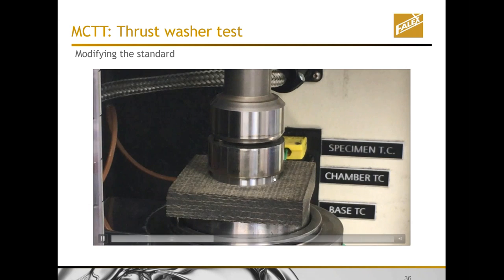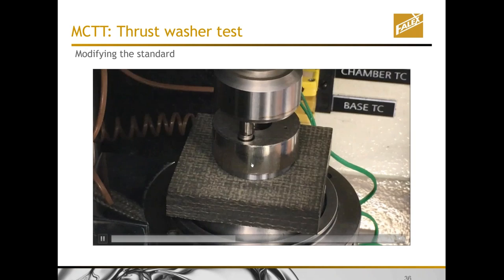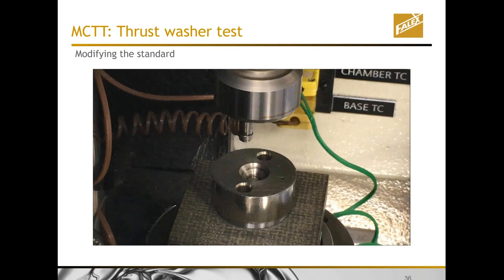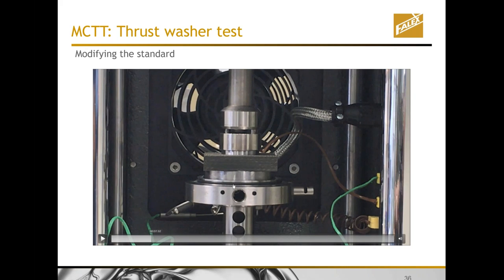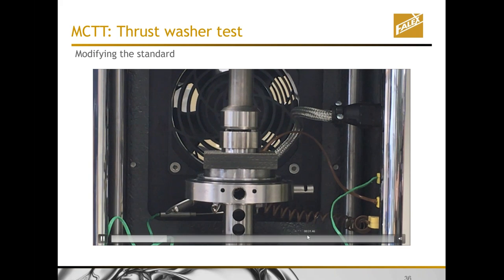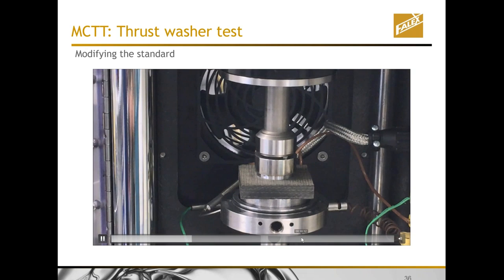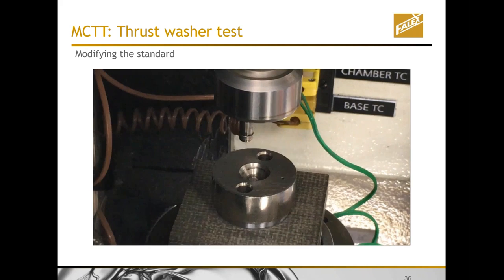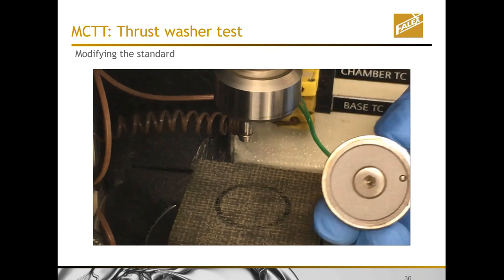We modified that method for some customers. In this modified method, the upper sample is a ring. What you see is the adapter holding the actual counter material — a ring of steel — while the lower sample is a composite material that wasn't possible to manufacture in the shape of a ring. No problem, because we can just fix this sample to another ring on our machine and do a test similar to a thrust washer test on different materials. You run the test for a predetermined amount of time, cycles, and load, and after the test, it's easy to take the samples apart and evaluate them.